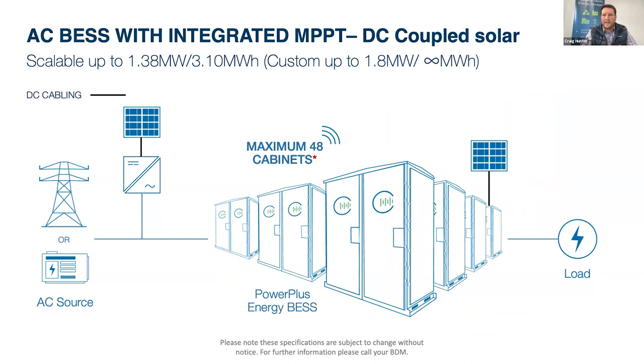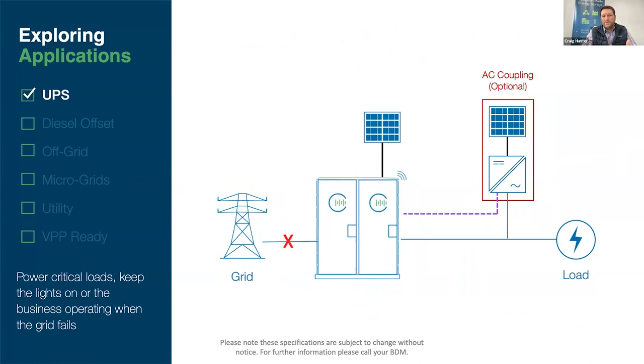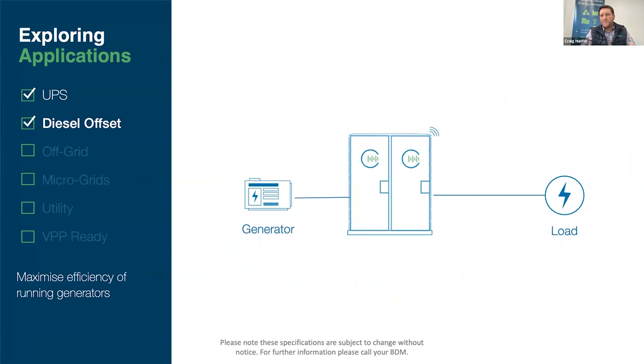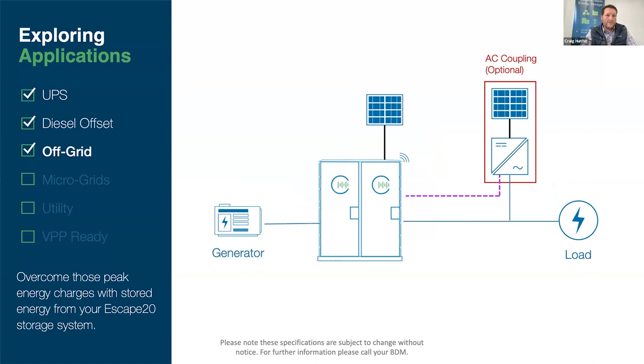When we look at applications, I mentioned it before, there's a UPS application. It's a true UPS, so you can use it for all those lovely applications. Diesel offset. A lot of people think that when someone's got a diesel generator, you need to add PV to it, but simply adding some battery storage to a diesel generator can definitely improve your return on investment and reduce the run costs on the generator. Off-grid applications, one of the key strengths of this product.